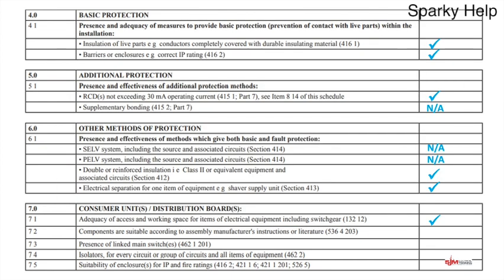Well, in a distribution board, what we mustn't start doing is putting a hodgepodge of different makes of circuit breakers and make them fit in the distribution board by bending the bus bar, filing a bit out of the lid to make it all go back on again. We're not allowed to do that. Anything that goes in must be confirmed that the manufacturer accepts it to be in that board. So it's just basically trying to keep everything the same and not mix and match between different makes and models. So hopefully that would be a tick.